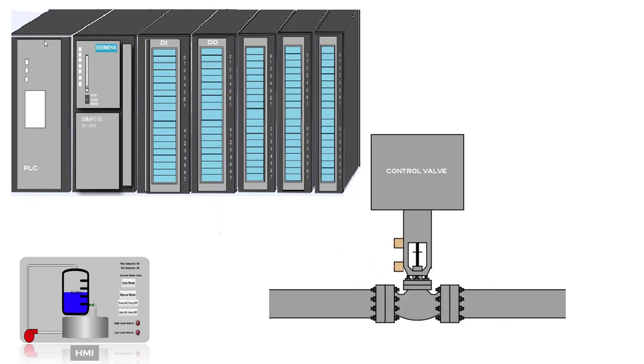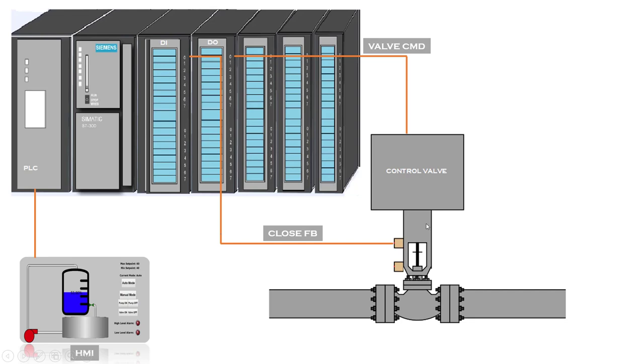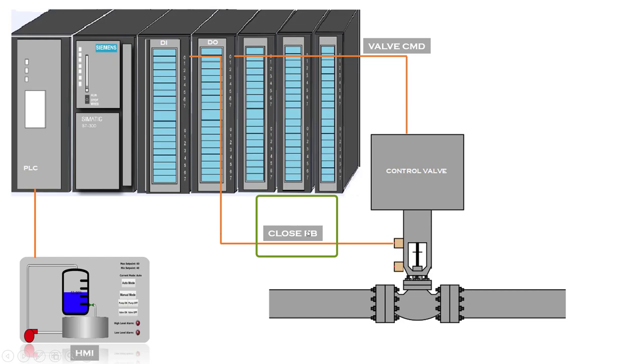If the operator decides to send a close command, this command will go to your PLC and PLC is going to send a signal from digital output card to control valve. The valve would be closed. You can see here the valve is closed and there is no flow coming through that. So we got another feedback which shows that the valve is closed.